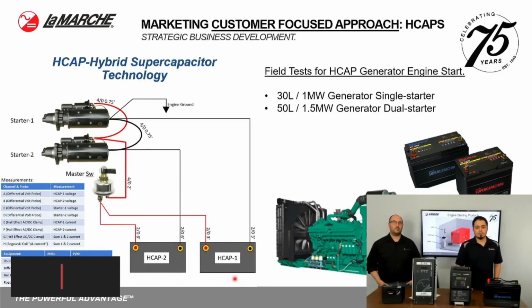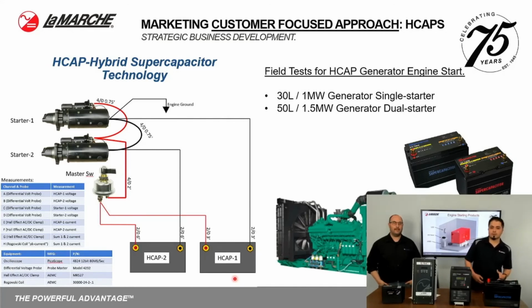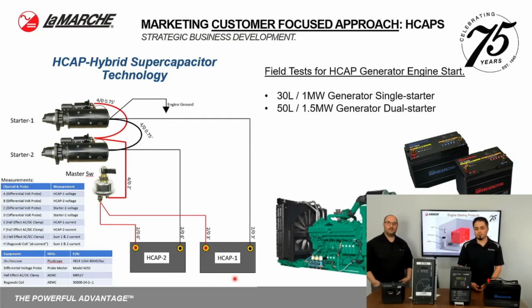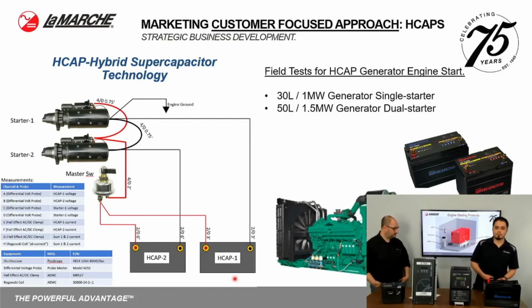So the first one being, again, that situation up north where we ran into a couple generators being 30 and 50 liter engines, 1 megawatt and 1.5 megawatt respectively. They ran into a situation where they had a very tight space. They were replacing these batteries regularly, 2 to 3 years apart. And they were just having a little bit more difficulty with the size and having to get people up there to make sure everything was correct every single time.